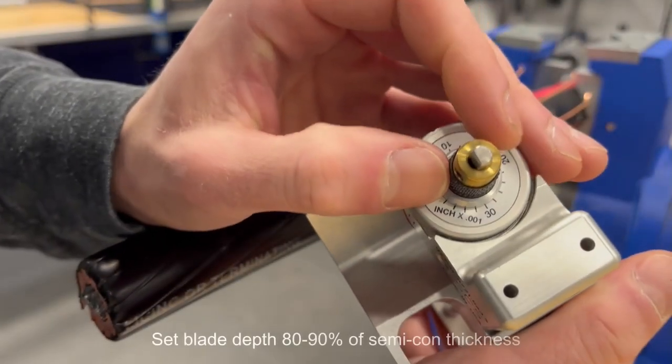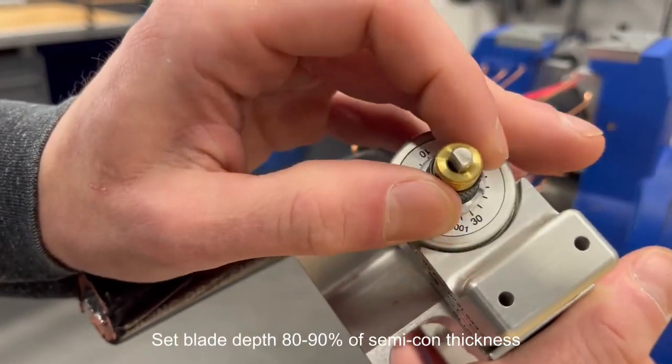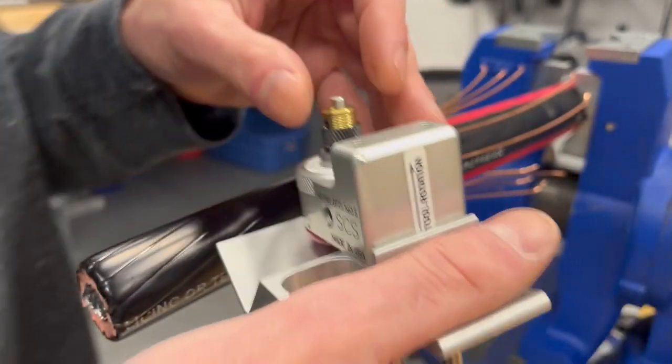Set the blade depth according to the SEMICON thickness. We're setting this one to 26 to avoid damage to the insulation.